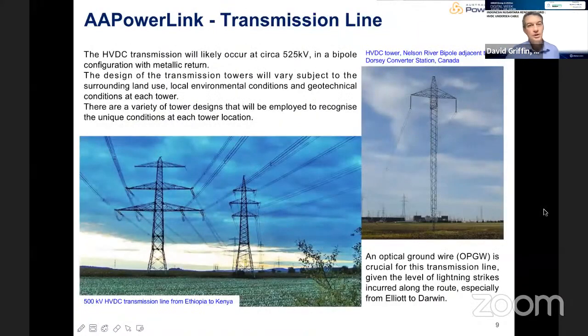With regards to the overhead transmission and indeed the entire high voltage direct current system, we are designing this as a 525 kV system. As a previous presenter noted, there are examples of overhead overland systems operating at 1100 kV, but we're really driven by the needs of the submarine cable system, trying to match everything up. 525 kV is becoming the standard for submarine cable transmission, which led us to adopt that voltage for the overhead system as well.